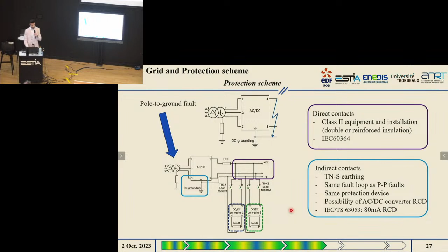And then I would like to show you the final protection architecture that was considered in this work, in which we added an AC protection device, an AC thermomagnetic circuit breaker associated with a 30 milliamp residual current device, that was put here in the case in which the converter is not capable of protecting itself, and the fuses and the DC thermomagnetic circuit breakers do not operate correctly.